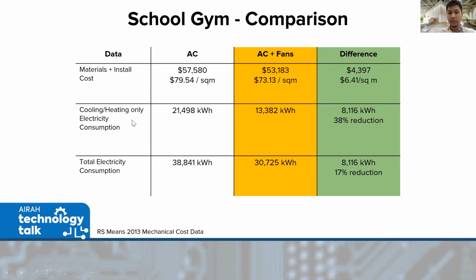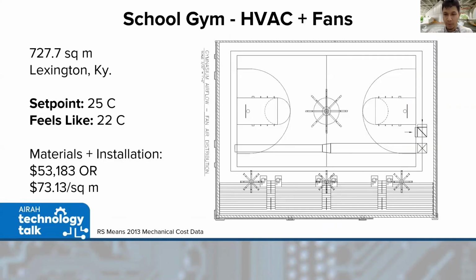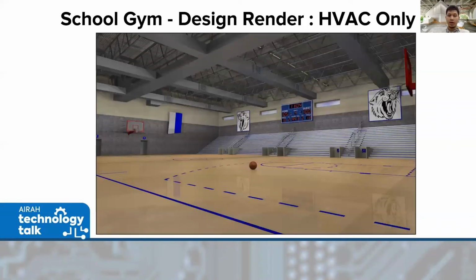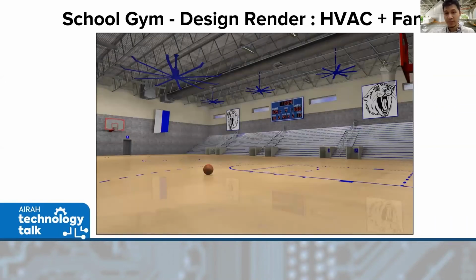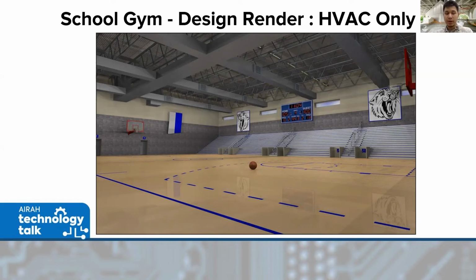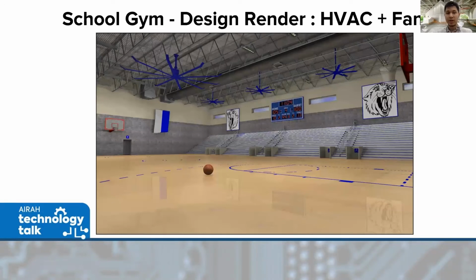For the cooling and heating consumption only, by using fans we achieve about 38% reduction for that facility, and about 17% reduction in total electricity consumption, just by incorporating those fans. We're incorporating 1, 2, 3, 4 fans there. This is the design render with HVAC, and also the design render with fans. As you can see, there's not much ductwork at the top, so you can save costs on that. And with fans, it opens up the roof space as well. It's an additional tool in your belt for you to use.